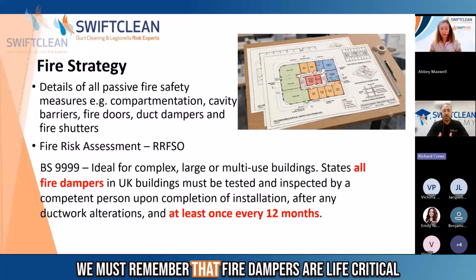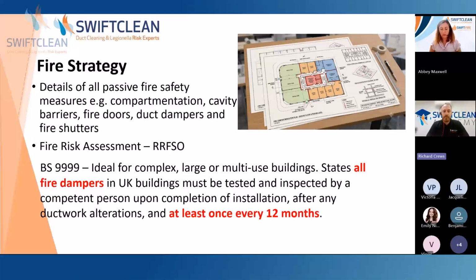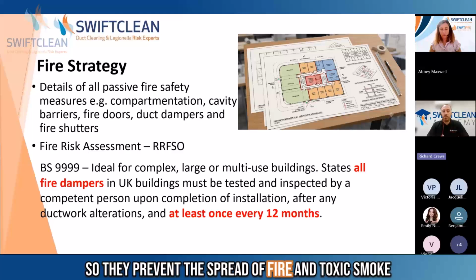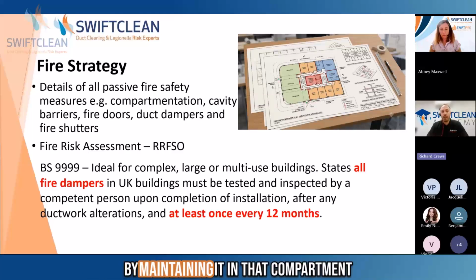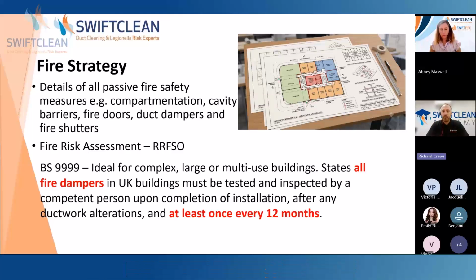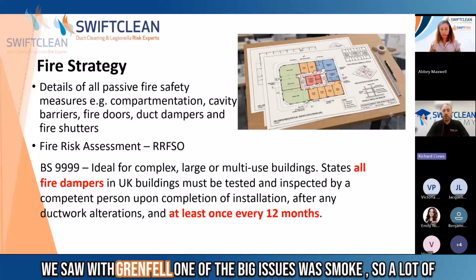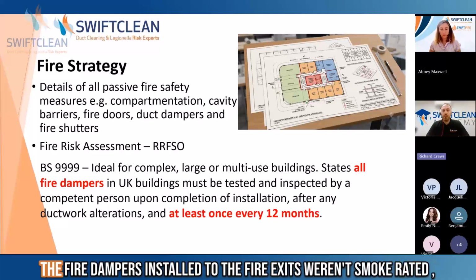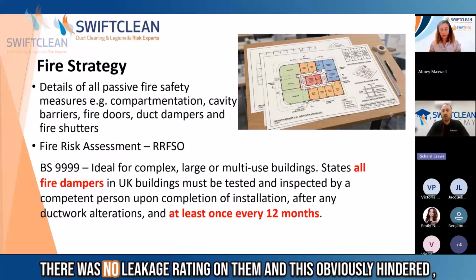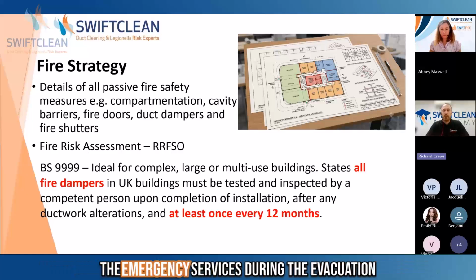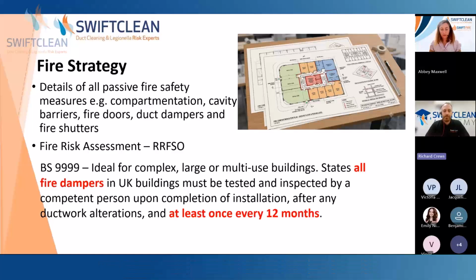We must remember that fire dampers are life-critical components. So they prevent the spread of fire and toxic smoke by maintaining it in that compartment. We saw with Grenfell, one of the big issues was smoke. So a lot of the fire dampers installed to the fire exits weren't smoke rated. There was no leakage rating on them. And this obviously hindered the emergency services during the evacuation.